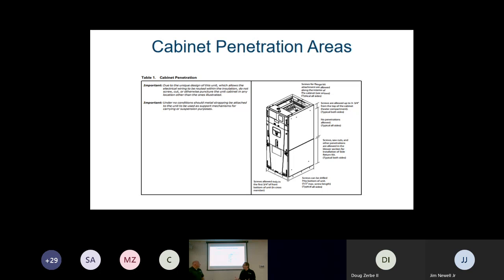Well, how many of us guys have bushings back down? And then when we started adding the bushings, we couldn't get our connector together, and the connector would be loose, and it wouldn't be a good seal. So now what they've done is the backside of the internal part of the fiberglass composite has been notched for something that large, but the outer cabinet has a starting point. You can see that starting point right here by this little dot.